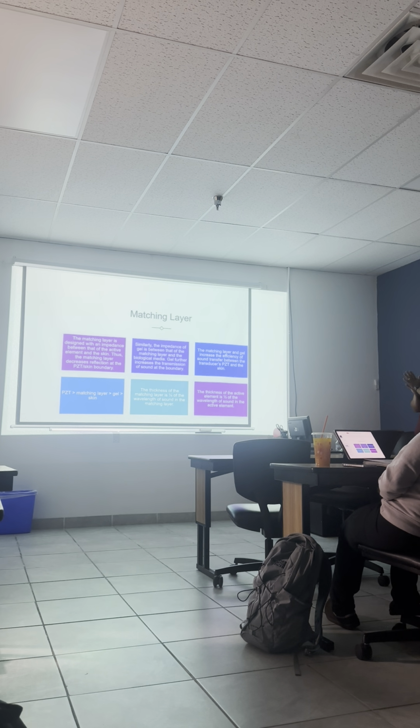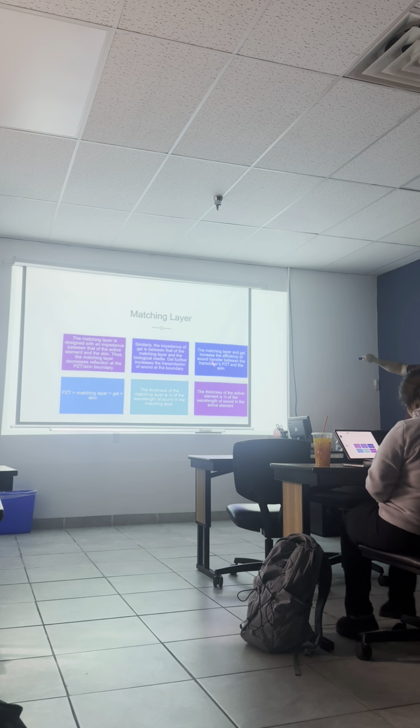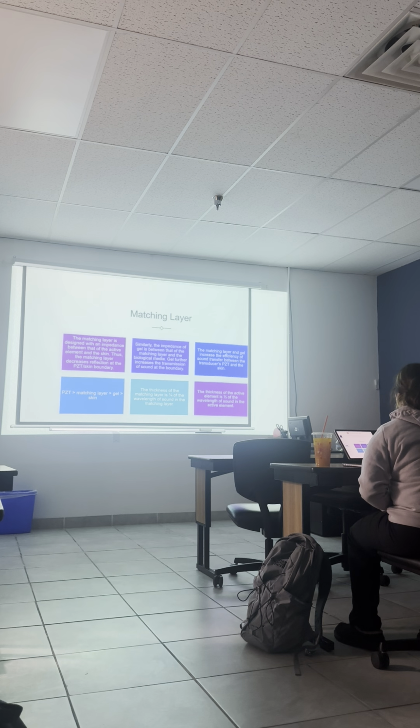Okay, so the matching layer and gel increase the efficiency of the sound transfer between the transducer's PZT and the skin. With this statement, what can we say about the attenuation between the PZT and the skin? Or the impedance? Without the gel, it's a big difference. So we can say that the impedance between the PZT and the skin has a big difference, or that the attenuation between the crystal and the skin has a big difference.